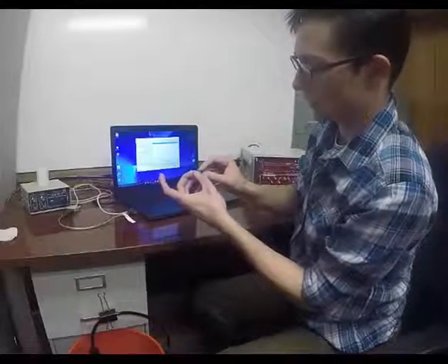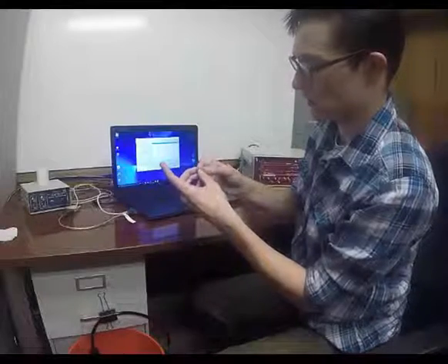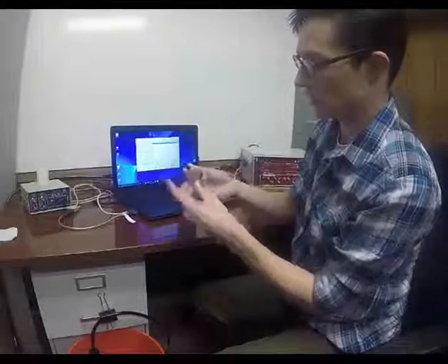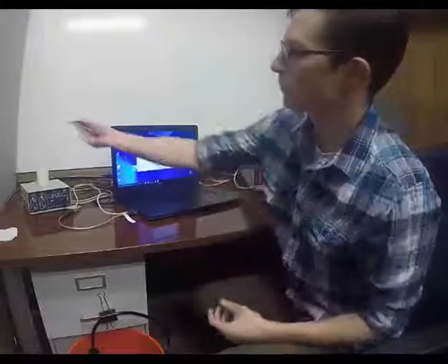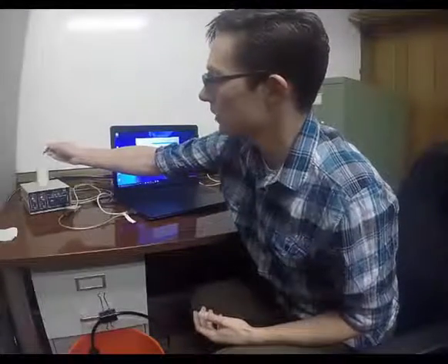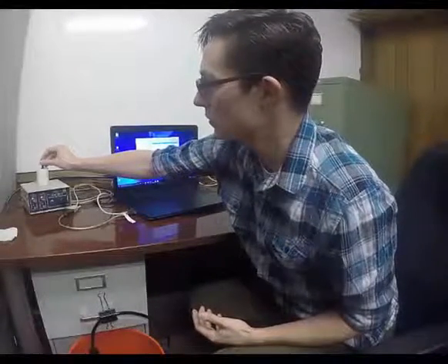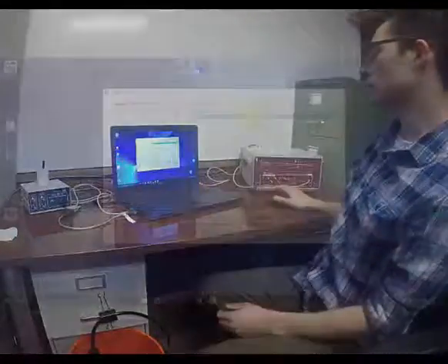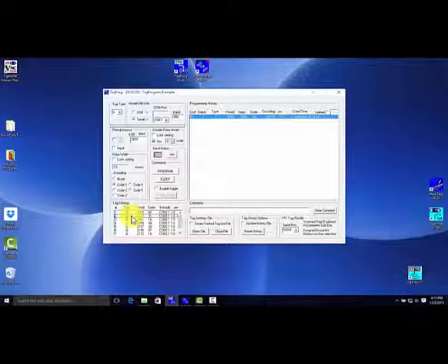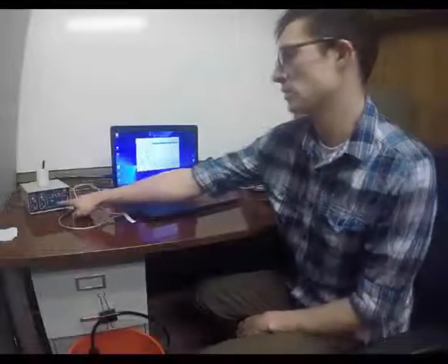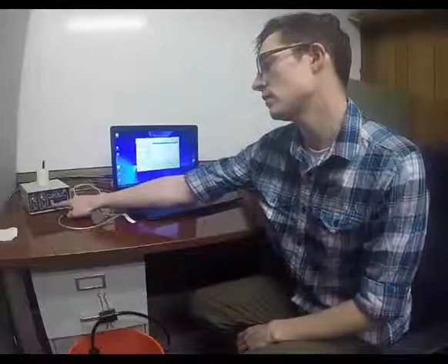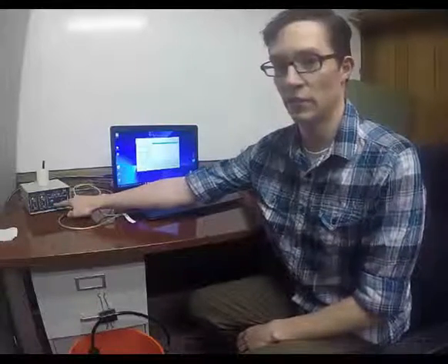So moving on to tag 2, I will do just the same thing. Very gently place it in our little straw. Place it clear end down into the coil. And on my software, this time I will select the second available tag settings option and come here and click program. Again, you see the Pulse Detect button flash and then begin to flash constantly at the rate of the period.